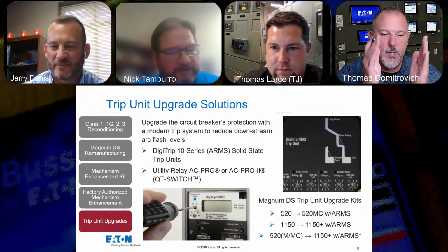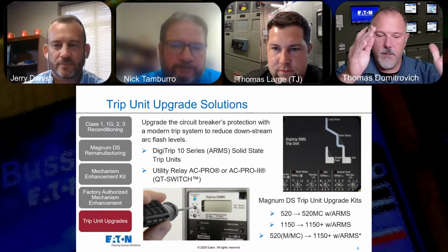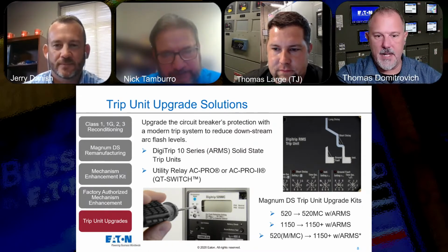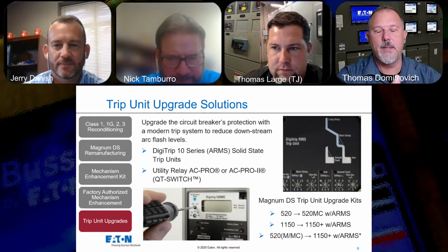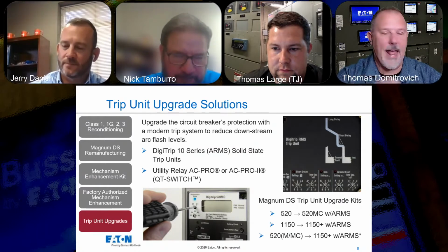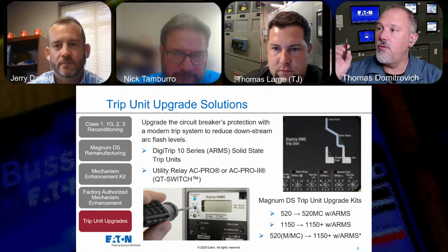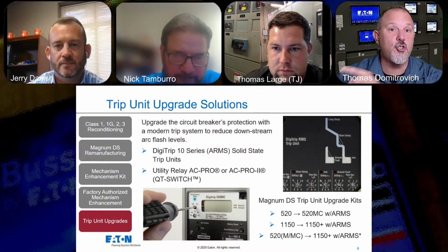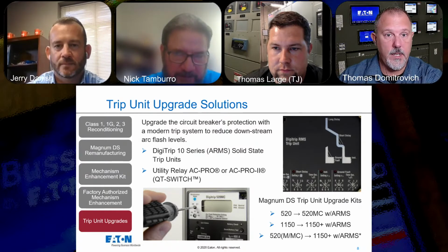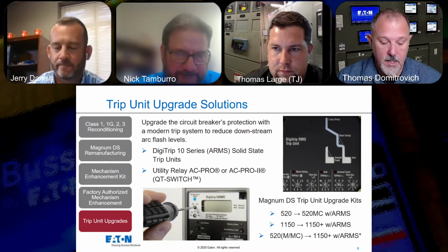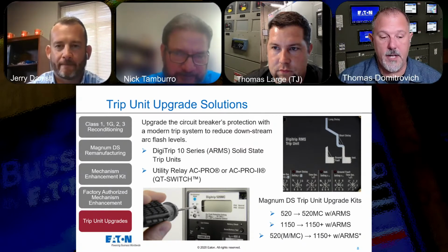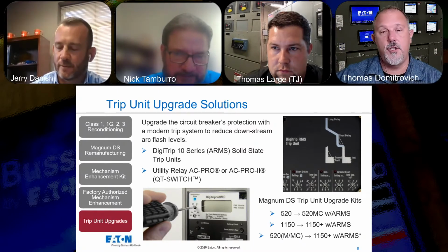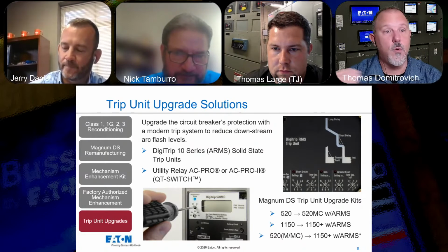So we talked about taking complete power circuit breakers down to the frame, and the process of that. We talked about the testing. We talked about adding trip units. You don't recondition or refurbish the trip unit itself, right? Correct, we do not. And that's not permitted by the National Electrical Code either. That was a new thing, that you can't recondition relays or trip units.